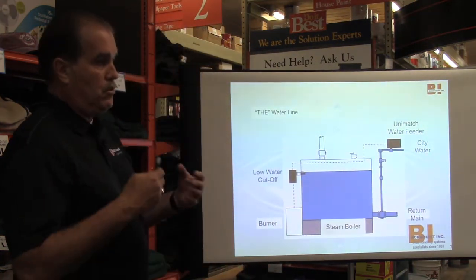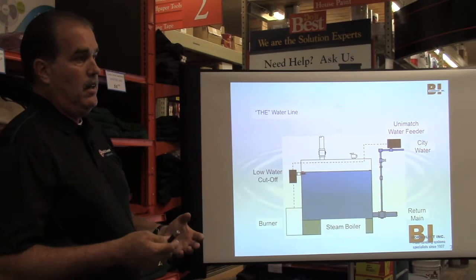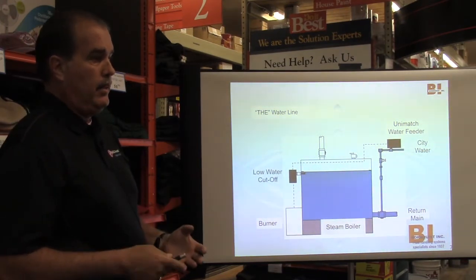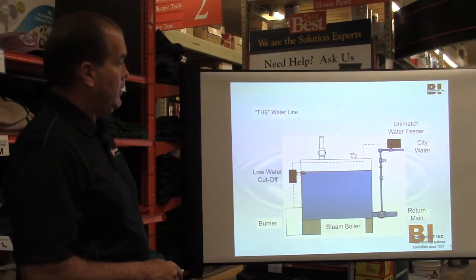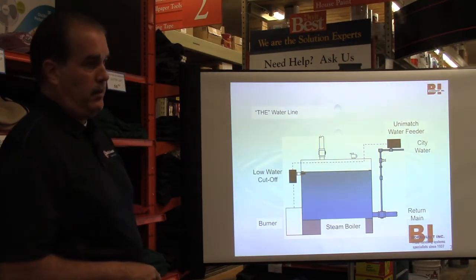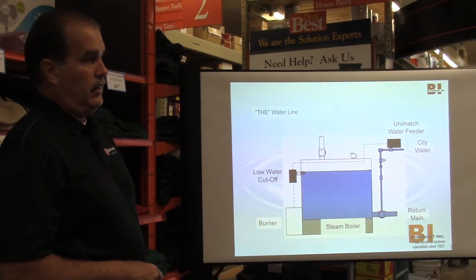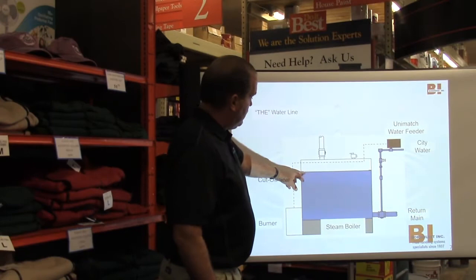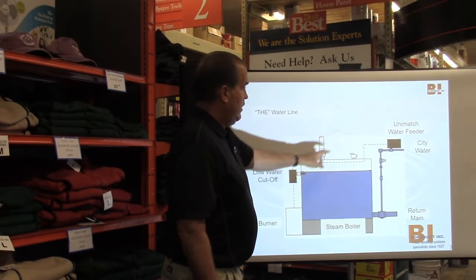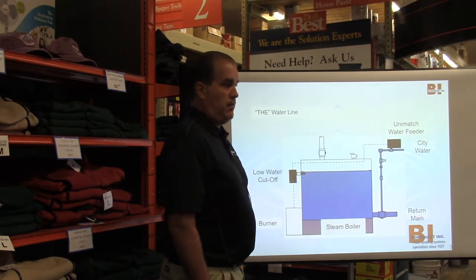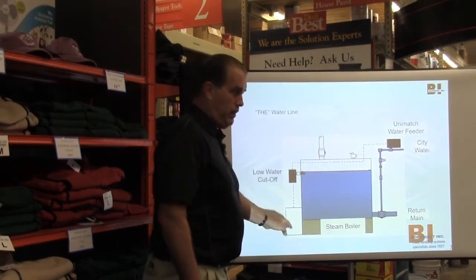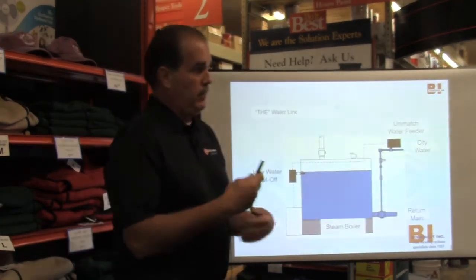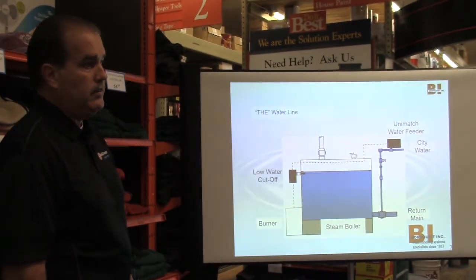Because steam systems do lose water over time. It's natural. You can't stop it. So now this water feeder is going to turn on, and then it's going to fill water into the boiler. Okay, and then as the water level rises, it goes above the probe. The probe senses that, turns the water feeder off, turns the burner back on, and now you're back to running your system as it's supposed to be run.